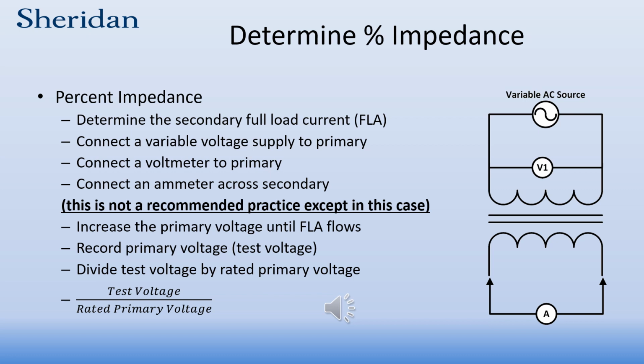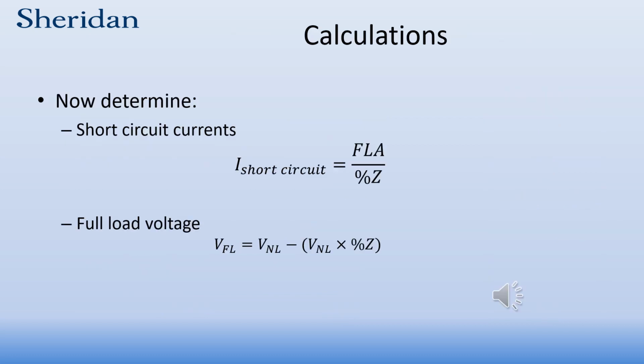This isn't recommended to do across any active transformer applying full primary current or full primary voltage. This will cause an accident, a real problem. So you increase the primary voltage until you get full load current flowing in the secondary. Record the primary voltage, that is actually what's called the test voltage, and you divide the test voltage by the rated primary voltage, and that will give you your percent impedance. With this value of percent impedance, it's possible to calculate short circuit currents of the transformer or full load voltage of the transformer.